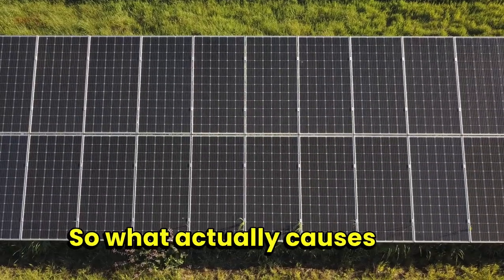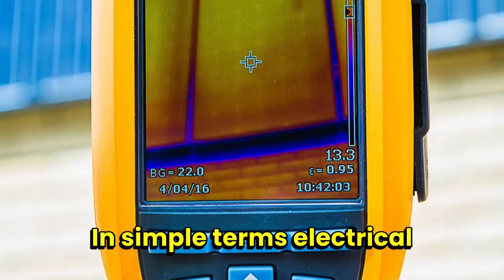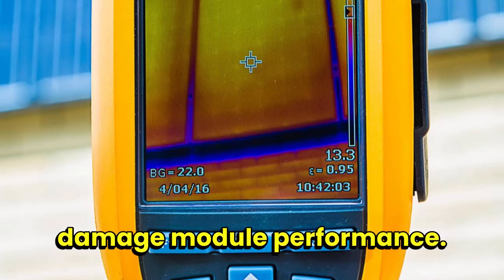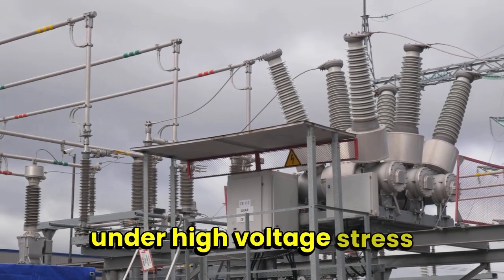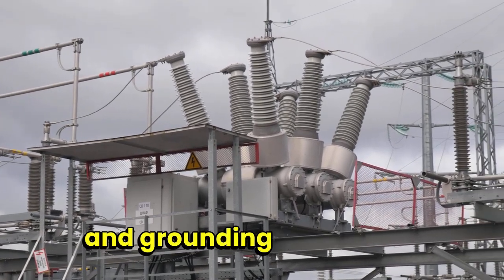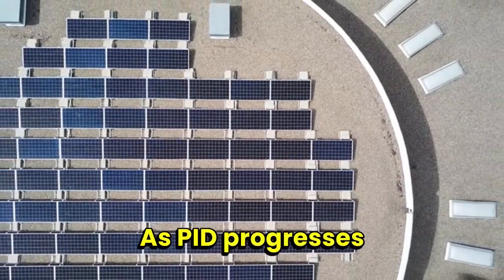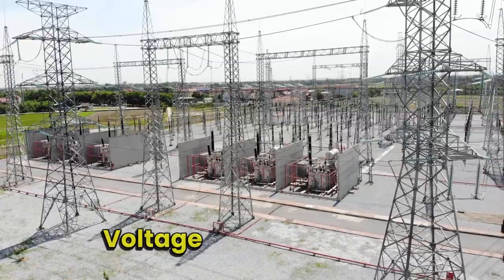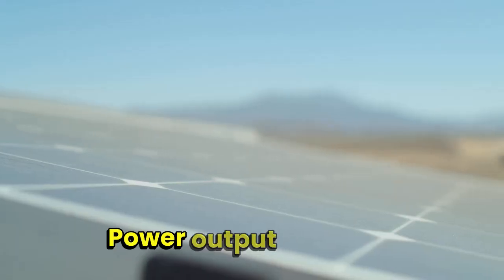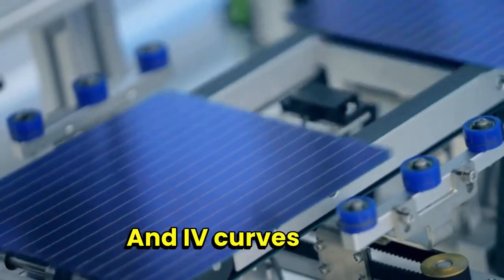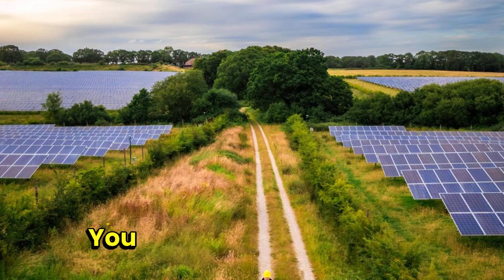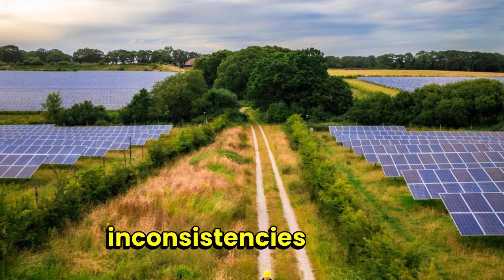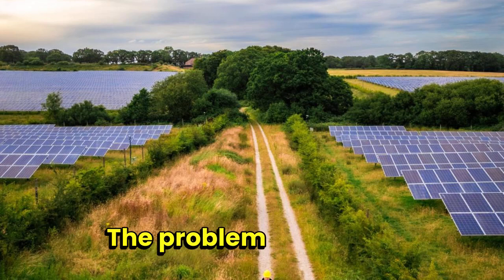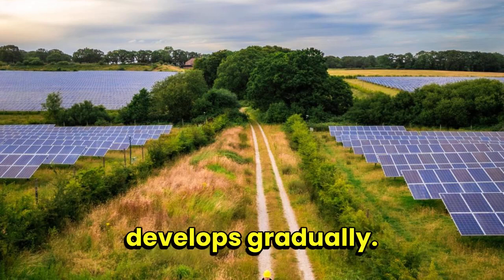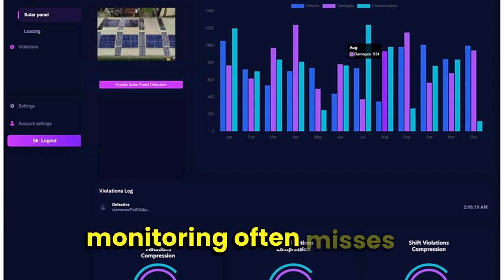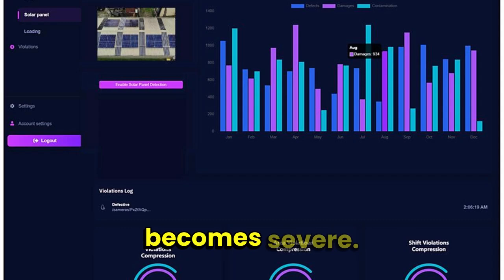So what actually causes PID? In simple terms, electrical leakage currents gradually damage module performance. This typically happens under high-voltage stress, combined with humidity, temperature, and grounding conditions. As PID progresses, module behavior changes. Voltage characteristics shift. Power output declines, and IV curves begin showing abnormal patterns. You may also see thermal inconsistencies across affected strings. The problem is that PID develops gradually, so standard production monitoring often misses it until the degradation becomes severe.